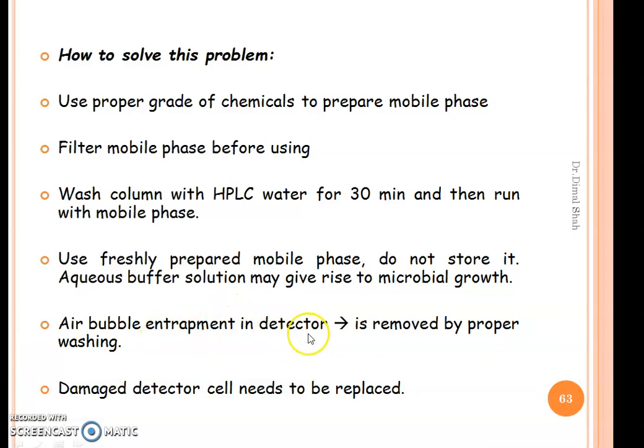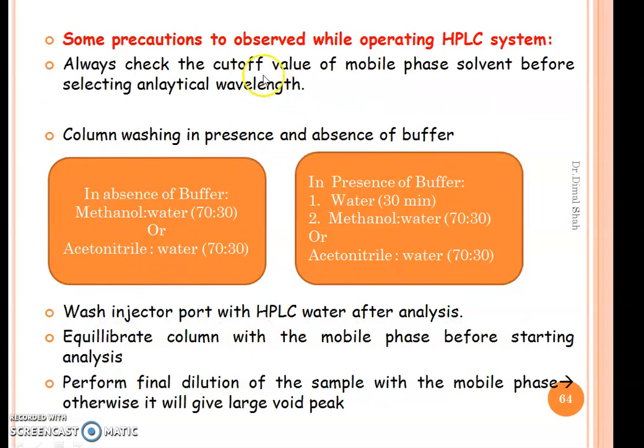Air bubble entrapment in the detector is removed by proper washing, and in case of a damaged detector cell, it needs to be replaced. Now, some precautions to be observed while operating the HPLC system. Always check the cutoff value of the mobile phase solvent before selecting the analytical wavelength.